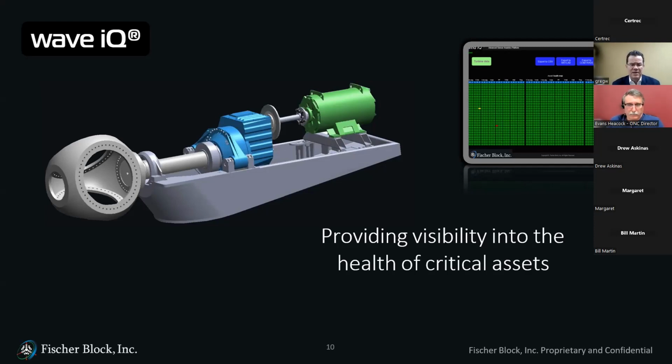But interestingly, that sun pinion is a recent use case. I think we're going to possibly talk about that later in this presentation, but we noticed a distortion not too long ago monitoring wind turbines, a 4 hertz distortion of about 0.1 or 0.2% of the total 60 hertz signal out to the grid. Consulting with the OEM of the gearbox, we confirmed the sun pinion operates at 4 hertz. They went in and did a borescope inspection, and sure enough, found a crack in the sun pinion gear. And so it's very interesting how, if we know the operating frequency of mechanical components, we can associate them on the front side and, immediately looking at the electrical signal, know where to go inspect.